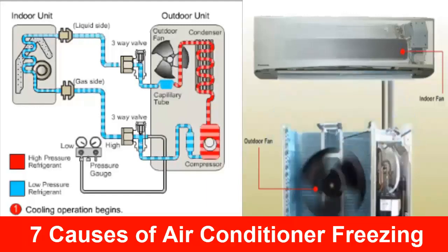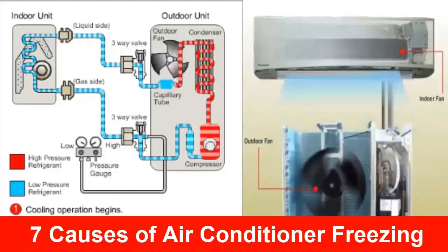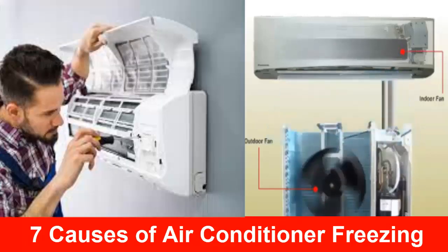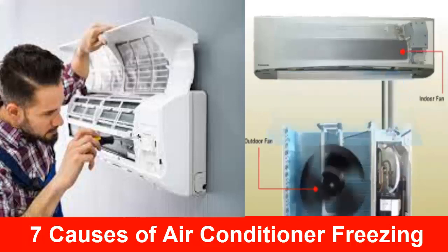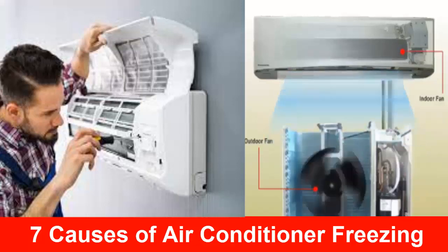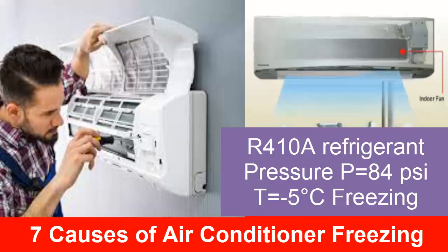1. Lack of maintenance. The air filter of the unit must be cleaned regularly to avoid clogging and blocking the airflow. When less air passes through the filter obstruction, there is not enough heat for the refrigerant inside the evaporator to absorb, thus lowering its pressure, which produces a temperature lower than normal, causing freezing.